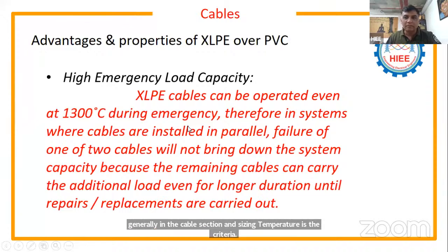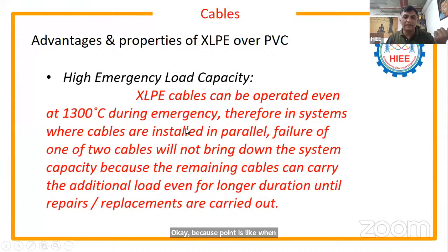Because the point is, when the temperature increases, your resistance increases. When the resistance increases, your conductivity will reduce. So temperature is the biggest culprit for cable sizing. That's where all these points come into the picture. High emergency load capacity when you're going with XLPE.